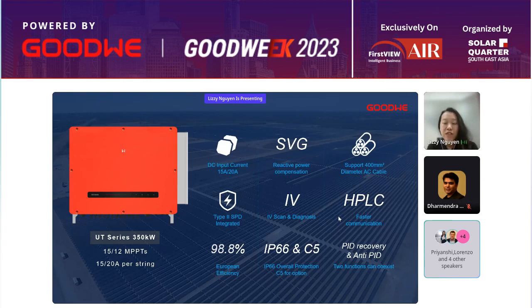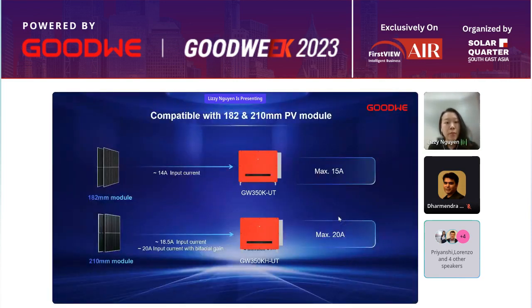For PID functions, we have two functions that can coexist at the same time, which are PID recovery and anti-PID. These functions are optional, and you can choose one or two at the same time. Our new products are compatible with 182 and 210 millimeter PV modules. For 182 millimeter modules, the input current of each string can go up to 14 ampere, and for 210 millimeter modules, it can go up to 18.5 ampere per string, or 20 ampere per string if it is bifacial.